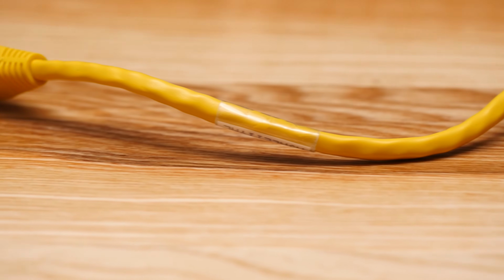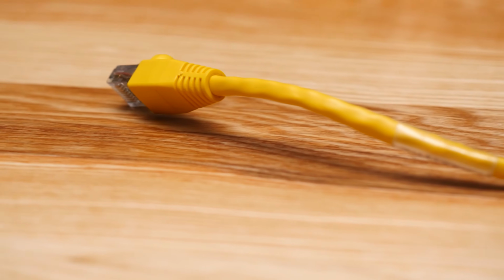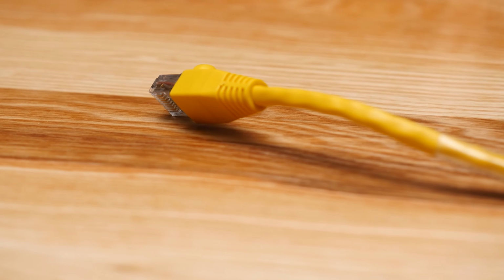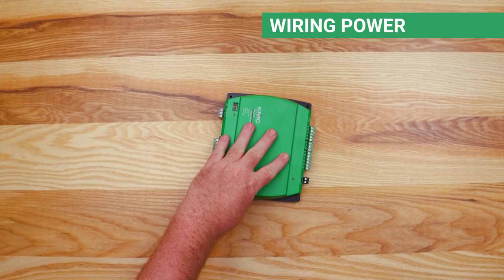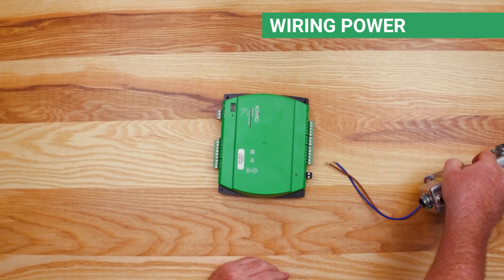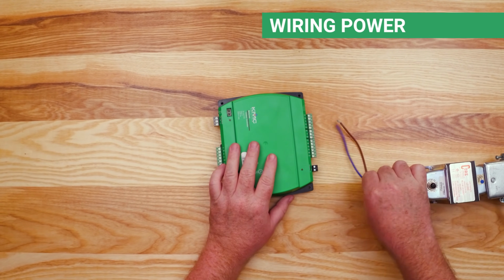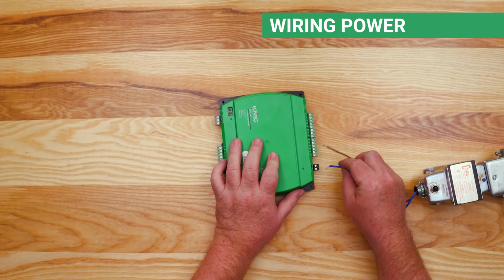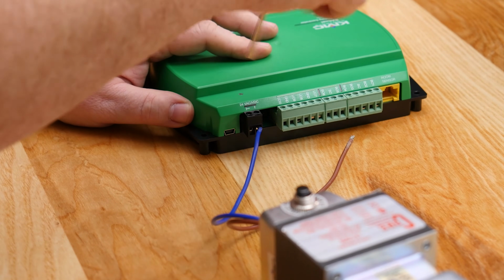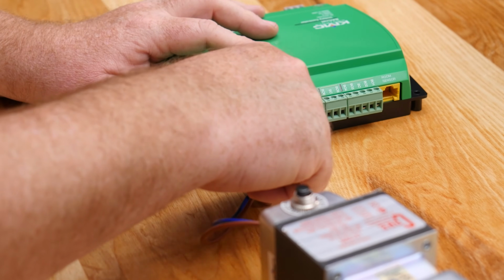Also, keep in mind that the Ethernet patch cable used for the room sensor can be a maximum of 150 feet long. The last step in wiring a BAC-9300 series controller is to connect the power. When connecting power, it is recommended that you use 18 to 24 gauge copper wire. Connect a 24 volt class 2 transformer to the black terminal block of the controller. The transformer should be dedicated to this controller.